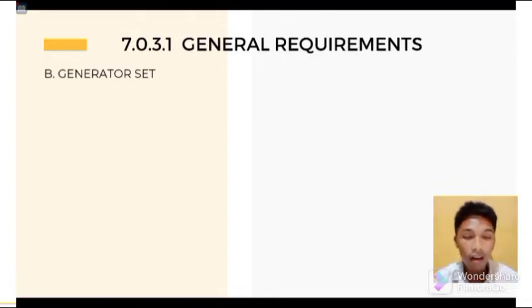Okay, so number 3, dual supplies. Prime movers shall not be solely dependent on a public utility gas system for their fuel supply or municipal water supply for their cooling systems. Means shall be provided for automatically transferring from one fuel supply to another where dual fuel supplies are used. So the exception for this is where acceptable to the authority having jurisdiction, the use of other than on-site fuel shall be permitted where there is a low probability of simultaneous failure of both the off-site fuel delivery system and the power from the outside electrical utility company.